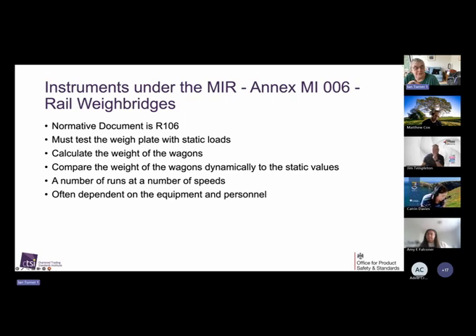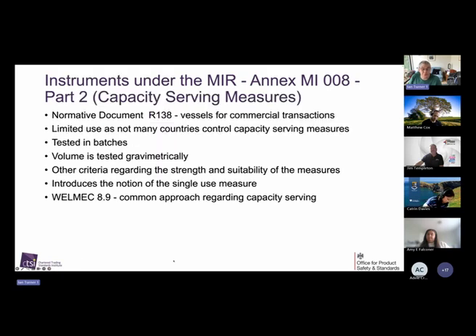And then rail weighbridges, normative document R106, must test the weigh plate with static load, calculate the weight of the wagons, compare the weight of the wagons dynamically to the static values, number of runs at different speeds. It's often dependent on the equipment and the personnel. Even the standard admits that you'll take 2 or 3 days to do it, probably. David used to do them, didn't he? Yeah, I think so. You used to go through to Fife and do the one at the power station at Longannet. I remember talking to David about them. So that's a run through automatic weighers. Questions, thoughts, experiences, anything to share?